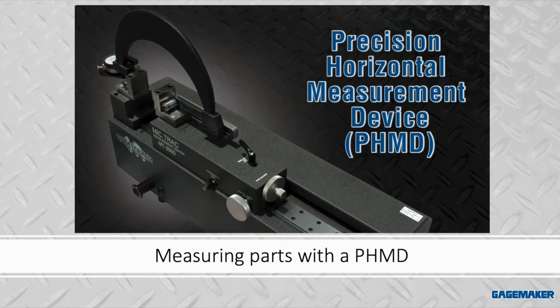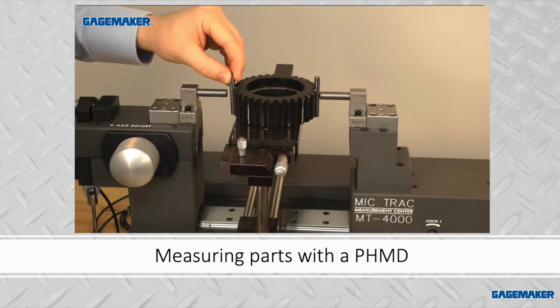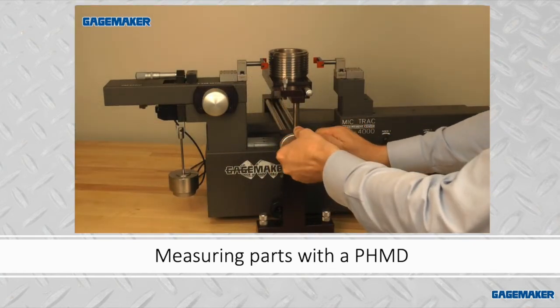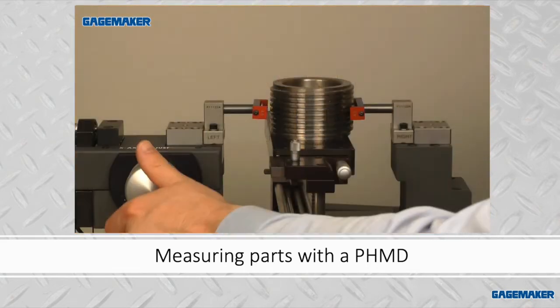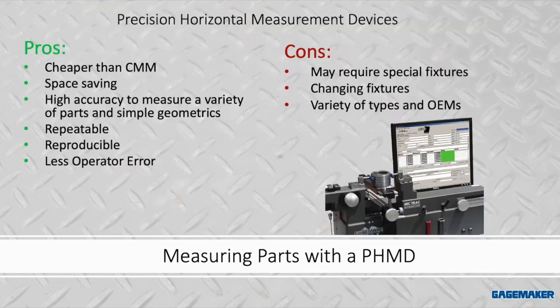So in contrast, let's consider measuring parts with a PHMD. So number one, this unit can be right out on the shop floor. Parts can come right out of the machine, go straight to the measuring device, and utilizing various apparatus and fixtures and support tables to be able to do a whole variety of parts. So let's examine some of the pros and cons of measuring parts with a PHMD. So these benchtop measuring devices, they realize immediate cost savings because they're only a fraction of the cost of a CMM. The CMMs and probe-style instruments or arms, they often go unutilized because of the amount of training it takes to get these going. So with a PHMD, you can measure parts immediately, right on the shop floor. The accuracy is there. There's high reproducibility, so you're not going to have a lot of error fluctuation between operators.